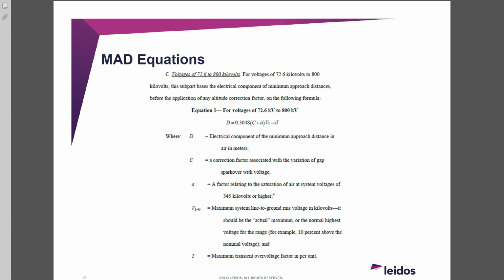I've never really heard of someone dying of a transient overvoltage. I'm sure it happens, but I hear about arc flash all the time, people getting hurt. It's a balancing act: if you reduce your minimum approach distance, your incident energy value goes up because you're closer to the arc, in theory. If you have really bad TOV, you're further away from the arc, but your PPE is really good. So this becomes an operations nightmare.